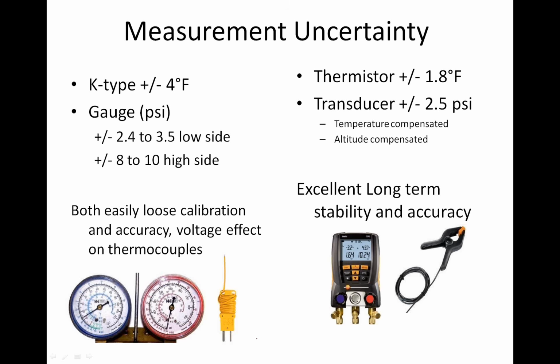Now, if you contrast that with a digital gauge set that uses thermistors, and Testo's not the only one, Digi-Kool does also, and I'm sure there's some other ones out there. But looking at it now, instead of plus or minus 4 psi or 4 degrees Fahrenheit, a thermistor is typically plus or minus 1.8. In transducers, because we're using a transducer to measure pressure, which they're typically made of ceramic, and they're typically 0.5%, they're much more accurate.